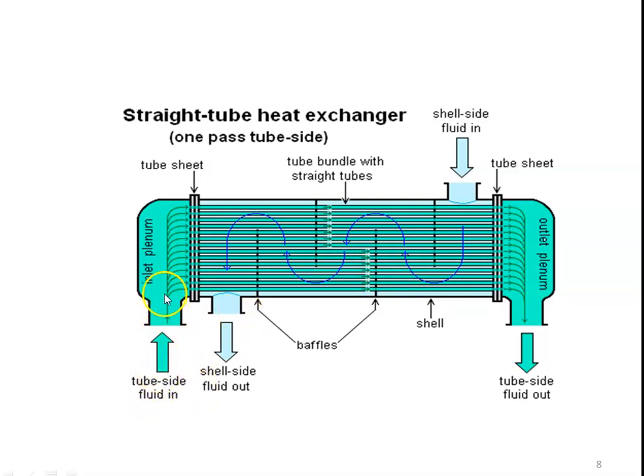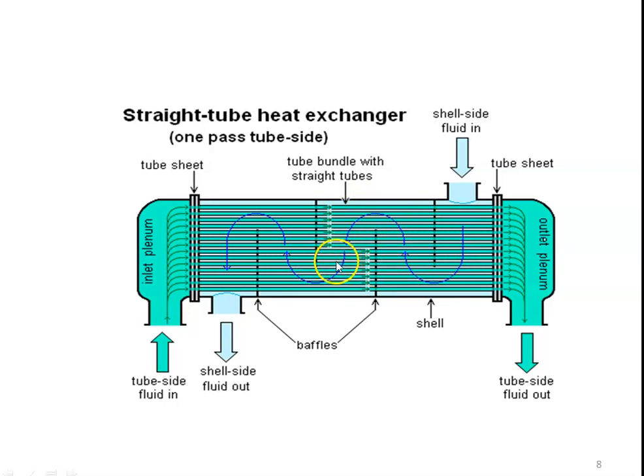The tube-side fluid enters and flows through the green-colored tubes from left to right, collects on the right side, and flows to the other connection. The shell-side fluid enters and the blue color line indicates its flow path. There are baffle plates whose purpose is to deflect the fluid so that the hot fluid is retained inside the heat exchanger for a longer time, increasing the length of the heat transfer path for more heat transfer between the hot and cold fluid.